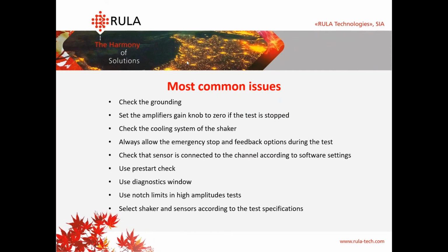And now let's talk about the most common issues we have. First of all, you need to check the grounding. On our devices, we have a special ground screw, and it's used for removing 50 Hz noise from the sockets.